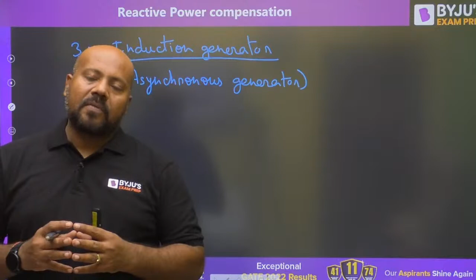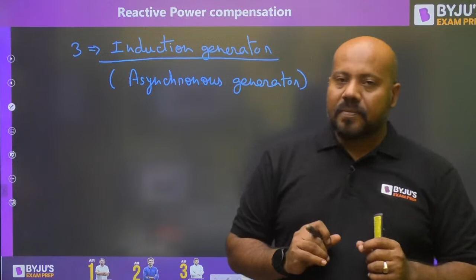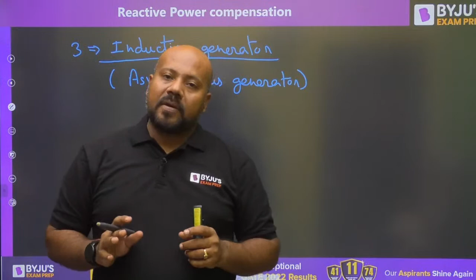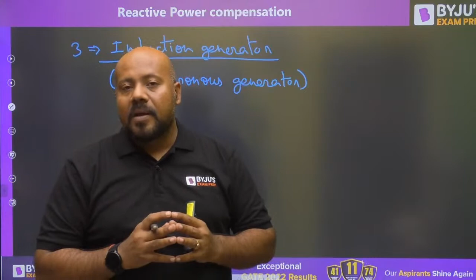What are the problems? Induction generator operates on the principle of induction. The principle of induction is the same principle that you are using in the transformer. Yes or no? What is induction principle? Induction principle means you give excitation to one winding or one system, and the other system currents are going to be induced. Now because of this nature, your induction generator cannot generate reactive power, and it can only generate real power. And for the reactive power, it is dependent on some external source.